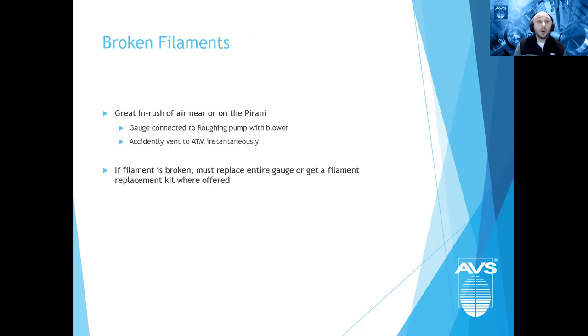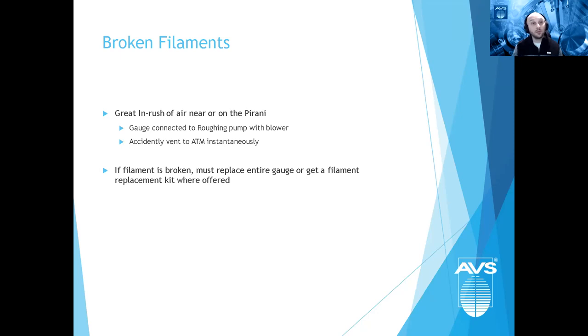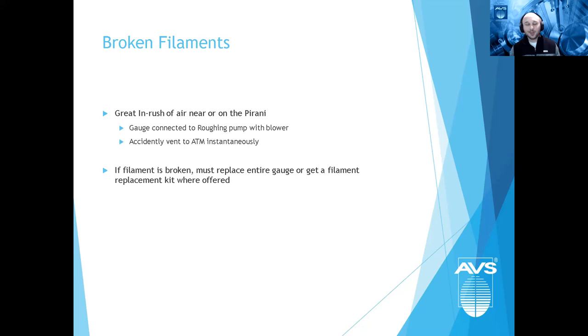Broken filaments are another failure mode, usually caused by a large inrush of air — accidental venting, or pumping down too quickly with a large roots blower. These filaments are very small and delicate; a significant inrush or back purge will likely break them. Most gauges will indicate this with a 'bad' reading or '999'. You then need to replace the gauge or use a filament replacement kit if one is available.